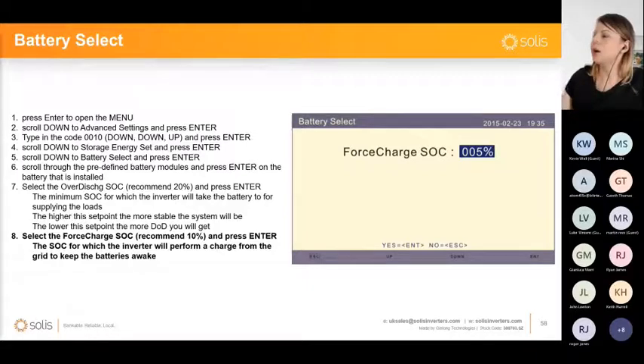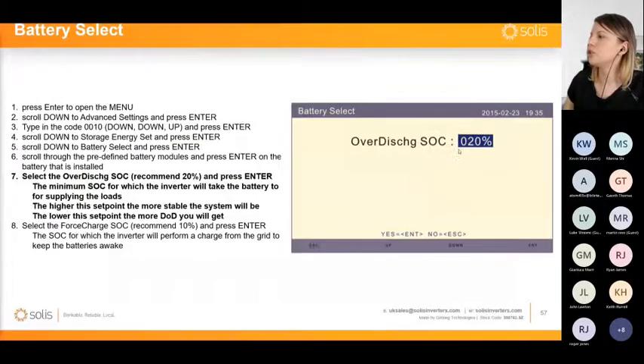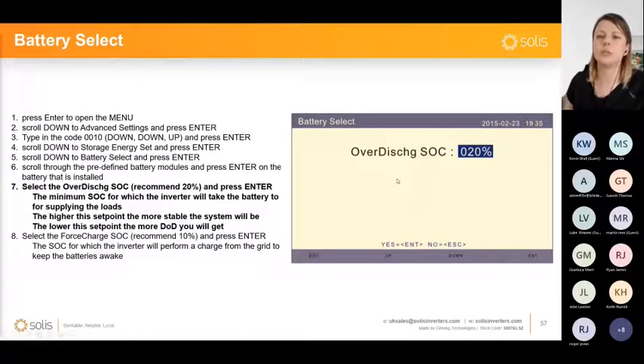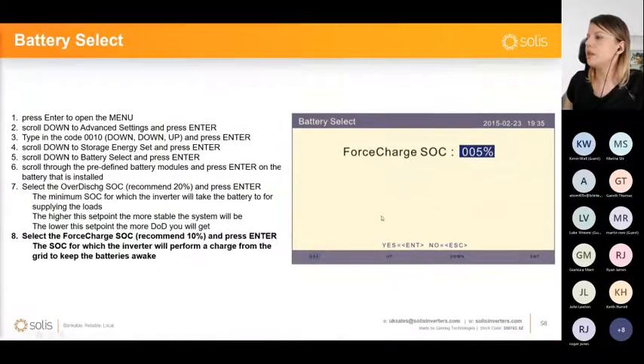When that value is set to not allow, and your state of charge gets below 5%, the inverter will not be capable of charging the battery from the grid in order to maintain that over discharge level. That's why it's highly recommended to have it set to allow. So when the battery gets to 5%, the inverter will start charging the battery with energy from the grid, and it will take it back to the over discharge SOC of 20%, just in order to keep it woken up and alive during those times with no PV available.